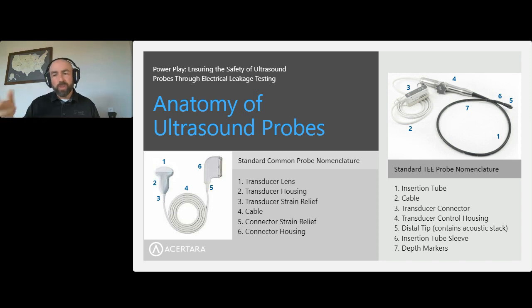When that happens, there are service providers out there that can correct that issue for you if your probes look that way. The connector strain relief on the other end actually typically gets a lot less strain than the one at the transducer side. And then finally, you have the connector housing, which typically has a lot of electronics in it. It is the connection into the system. Sometimes you have multiplexing in that connector. Sometimes you have it in the head. But either way, there's typically a lot of electronics.